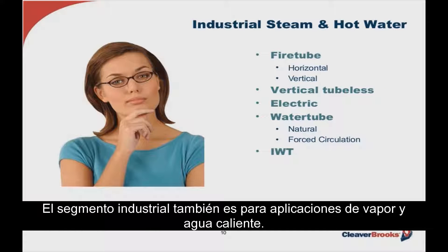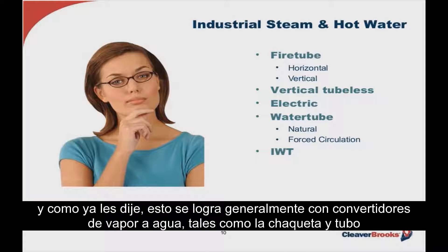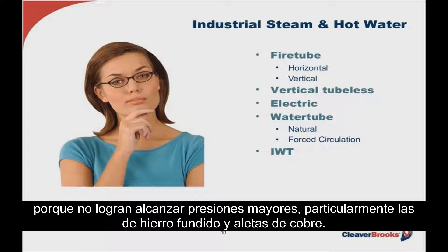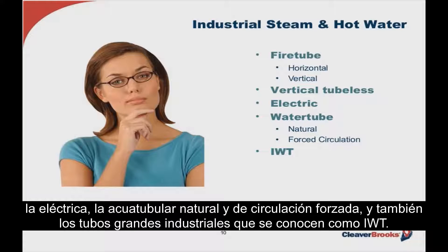The industrial segment is also steam and hot water applications, with the emphasis on process steam, though comfort heating can be included — normally accomplished with a steam-to-water converter such as a shell and tube heater or a plate and frame heat exchanger. Boiler types are somewhat similar to commercial products, though cast iron and copper fin boilers have been eliminated due to their inability to achieve higher design pressure. In the industrial segment we have fire tube boilers, the vertical tubeless boiler, electric, water tube both natural and forced circulation, and large industrial water tubes, also known as IWTs.